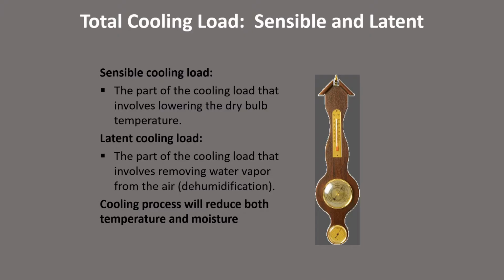So yeah, just going over the definitions of sensible and latent cooling load. The sensible is that part of the cooling load that involves lowering the dry bulb temperature. And dry bulb, this means a regular thermometer. If you put it in your house, or put it outside, that's the dry bulb temperature that you're getting. The latent load, that's the part of the cooling load that involves removing water vapor from the airstream. In muggy climates, this is critical.